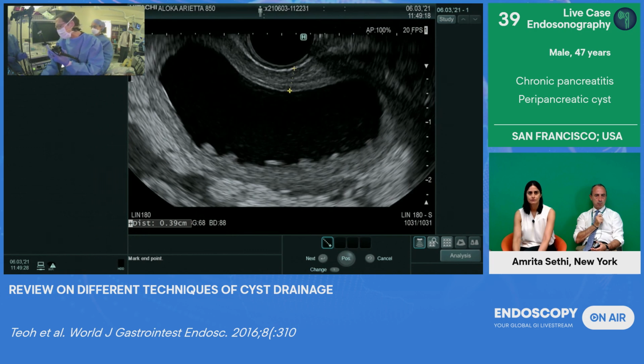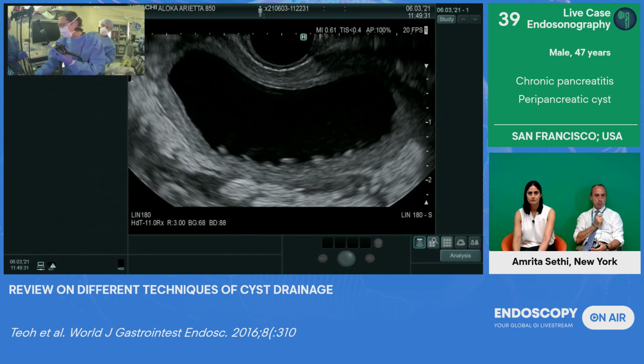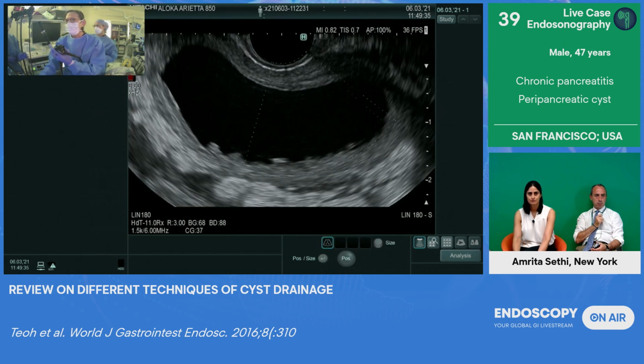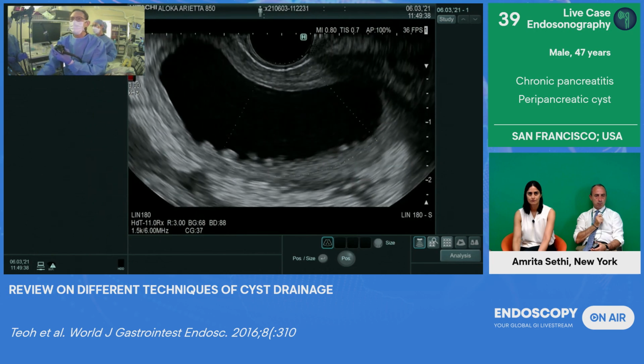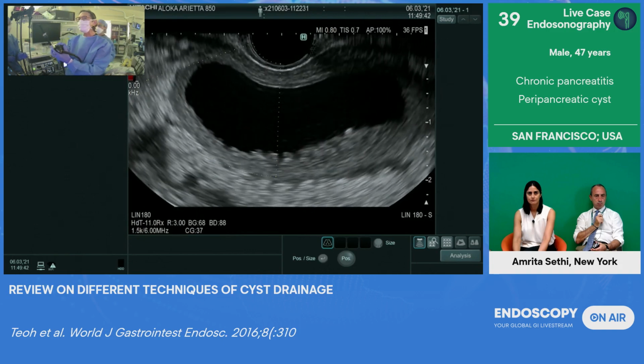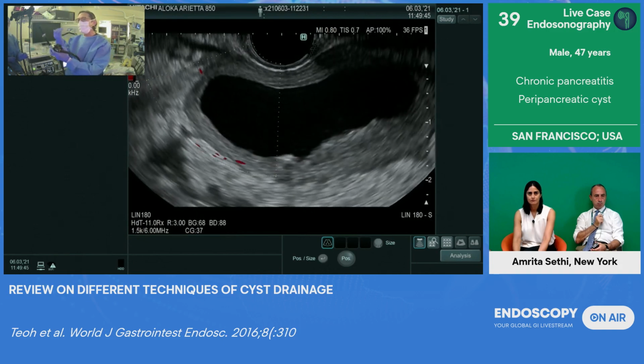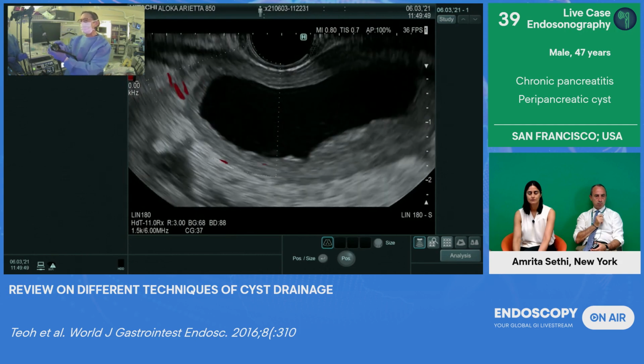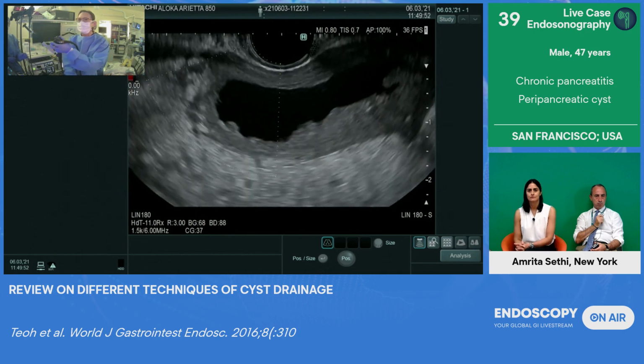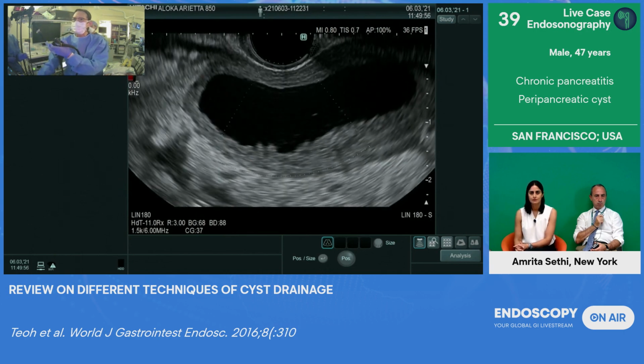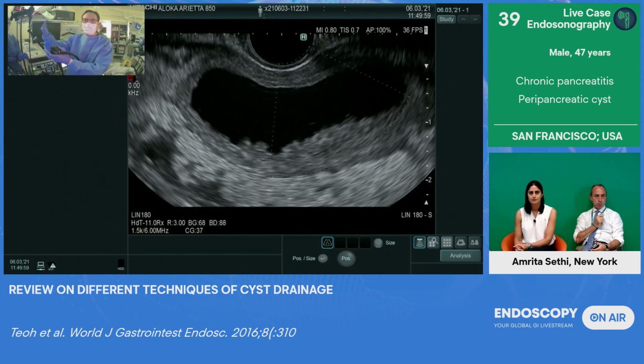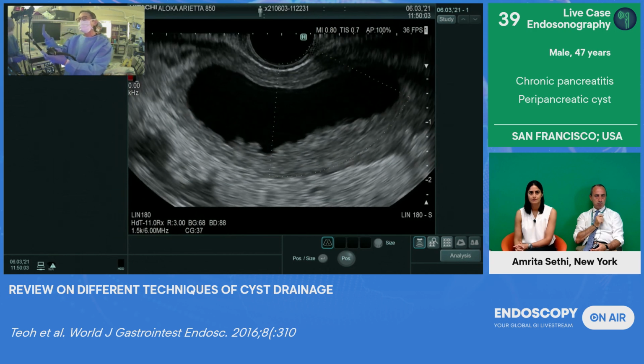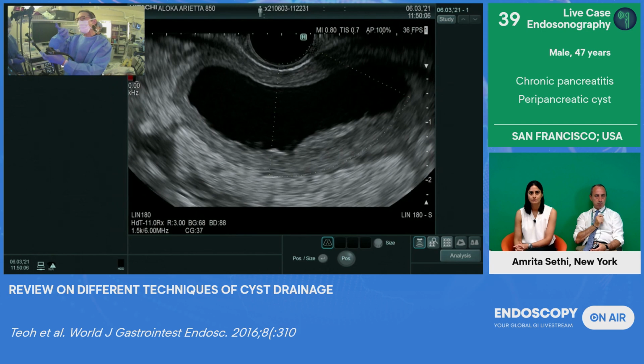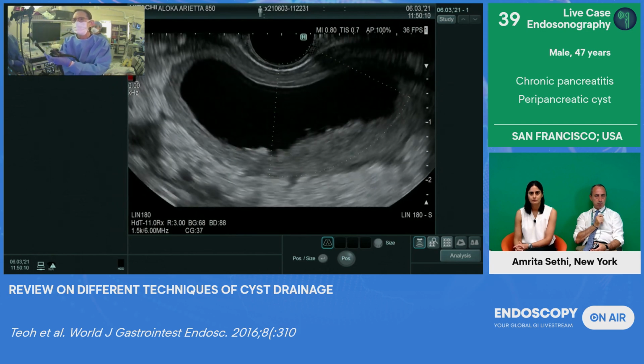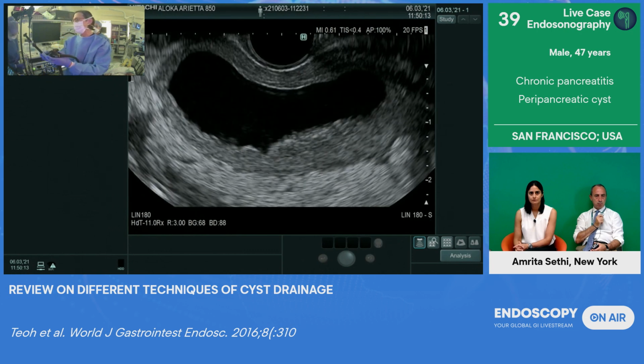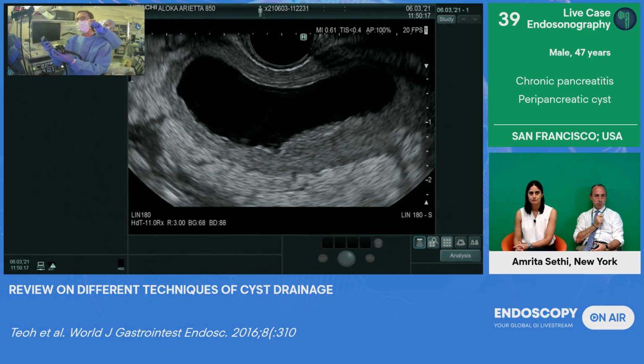And the other thing I should emphasize is that you always switch on your Doppler. You should make that a routine habit to always check the wall for interposed vessels. And when you do that, you need to release your transducer so you're not compressing the wall with your transducer. So with the up-down wheel, release that pressure against the wall to see if there are any interposed vessels and just scan around. Remember, when the flange opens up, it's going to open to a diameter of almost 3 centimeters, right? Then you don't want to have that flange close to a vessel if possible. All right, so I'm going to turn the Doppler off now, and we will proceed to advance the sheath out.